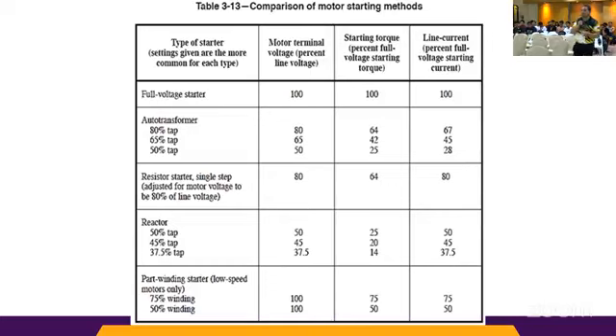Okay, so meron tayong full voltage starter for 100%. Then we have auto transformer, depende, 80% tap, 65% tap, 50% tap. We have also resistor starter, tinatawag na primary and secondary resistance reduced voltage starter. Then we have the reactor, 50% tap, 45% tap, 37% tap. Then we have also part winding starter for low speed motor only. So 75% winding, 50% winding. So just to control the voltage drop of the motor. Next.